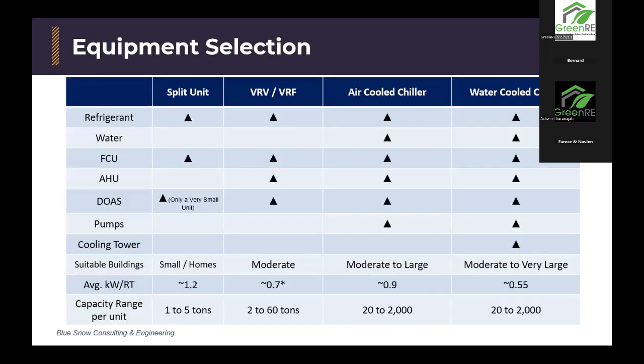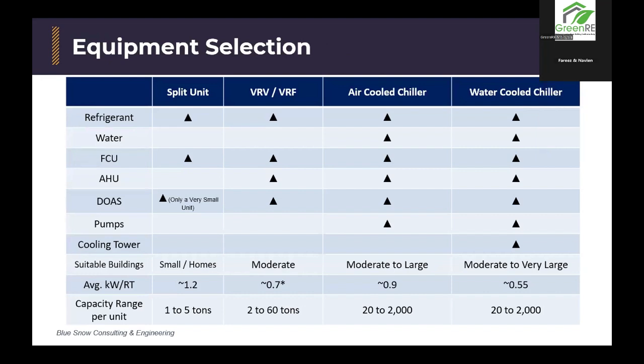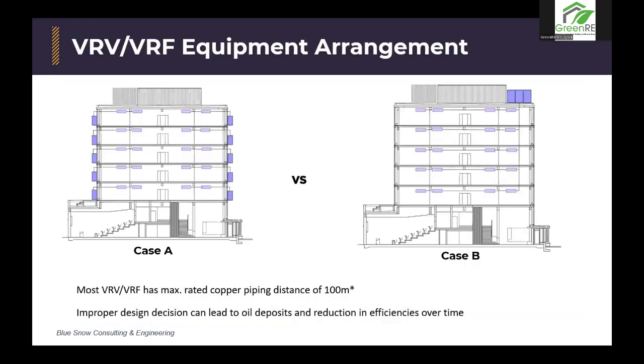So like this efficiency here, like earlier you've seen, 0.7, this is often the efficiency you can get at the start. That means you just build the building, you commission your system, you can get this efficiency, not an issue. But after 5 years down the line, it may be worse than an air-cooled chiller. So what kind of issues can lead to that? A VRV and VRF system actually has to be designed in a very careful manner. Case A is, for example, this right here. This is the outdoor unit. This is the indoor unit.